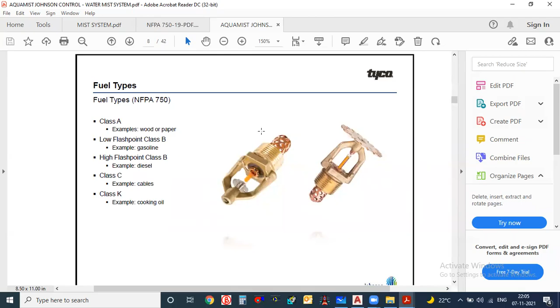Here you can see applicable hazards too: combustible turbine, generator, hydraulic pump room, machinery spaces, chemical fume, data center, hospital, hotels, office buildings, and residential buildings classified as light hazard under NFPA 13, though not applicable for NFPA 13R or 13D residential systems.